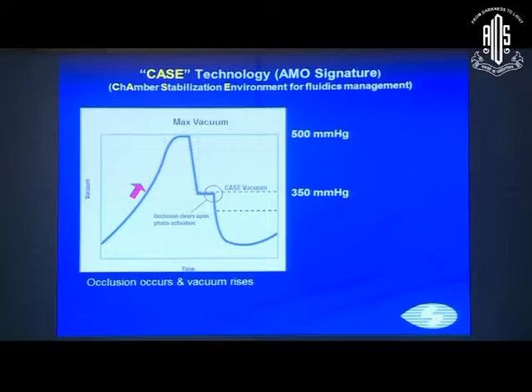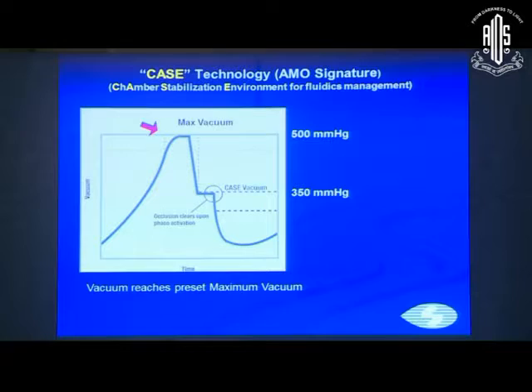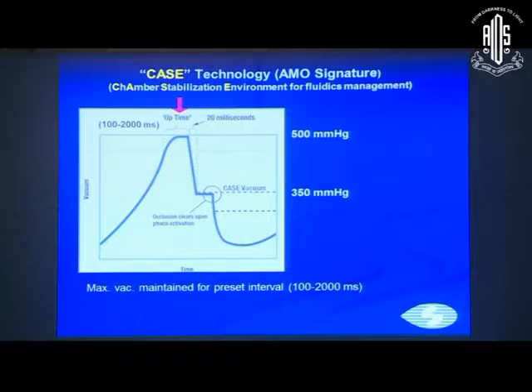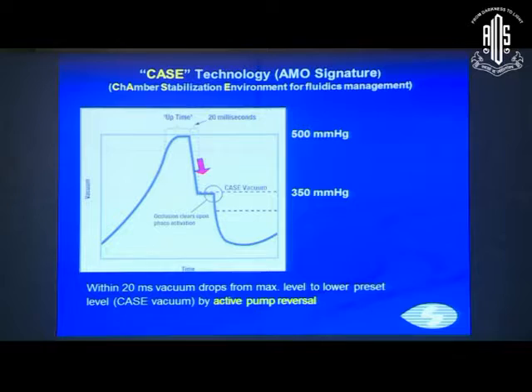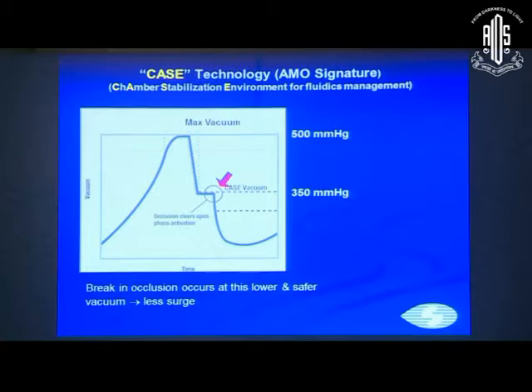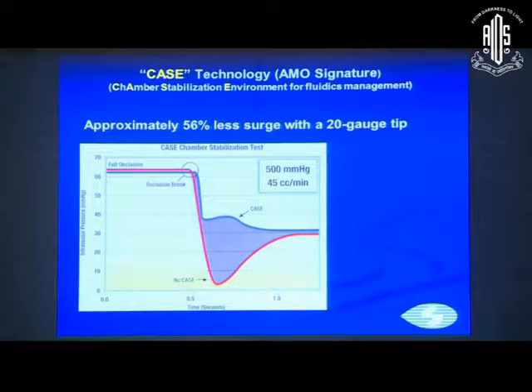The CASE technology — Chamber Stabilizing Environment for fluidics management — works as follows: when occlusion occurs, vacuum rises to a preset maximum of about 500 mmHg, which can be maintained for 100 to 2000 ms. Within 20 ms, the vacuum drops by active pump reversal to a lower level called the CASE vacuum, set at about 350. When the occlusion finally breaks, it does so at the lower CASE vacuum rather than at the maximum, resulting in less surge — reducing surge by approximately 56% with a 20-gauge tip.